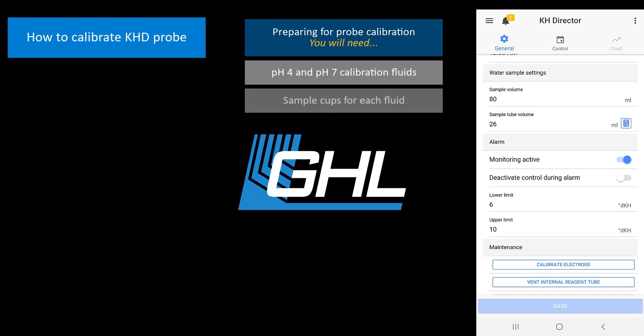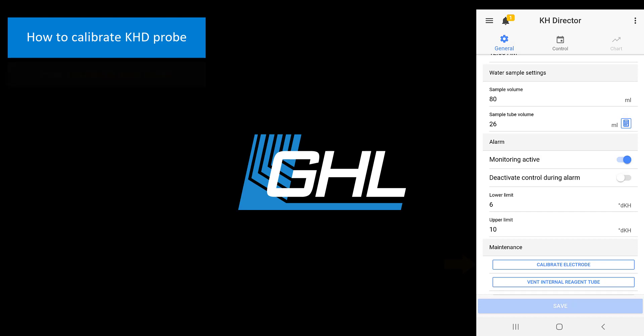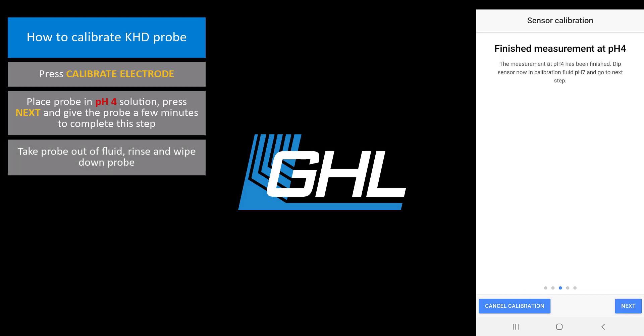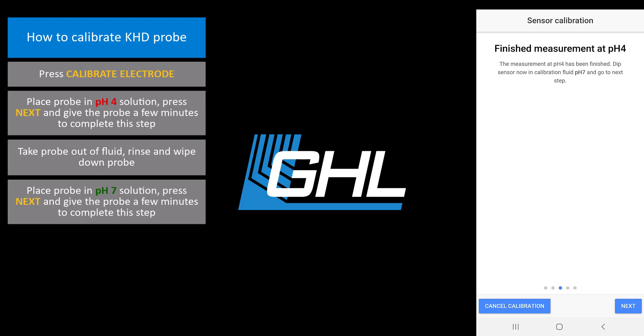You will also need two sample cups for holding small amounts of each fluid. You can prepare these samples by pouring pH 4 fluid into one cup and pH 7 fluid into another cup. In the Maintenance section, press Calibrate Electrode. Take the KHD probe and sit it in the sample of pH 4 fluid, then press Next. Give the probe a few minutes to complete this step. Take the probe out of the fluid, then rinse and wipe down the probe. This will prevent any cross contamination between the calibration fluids and water used for rinsing. Place the probe in the pH 7 fluid, then press Next.